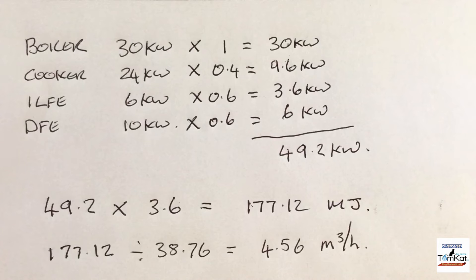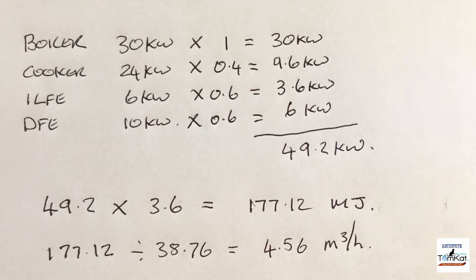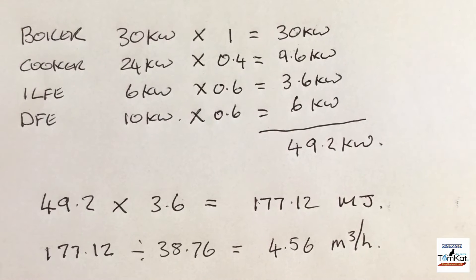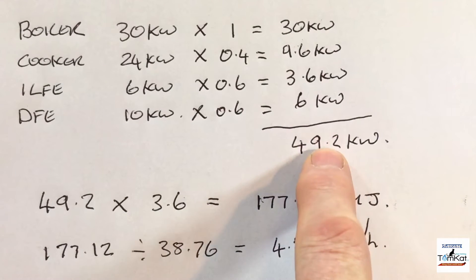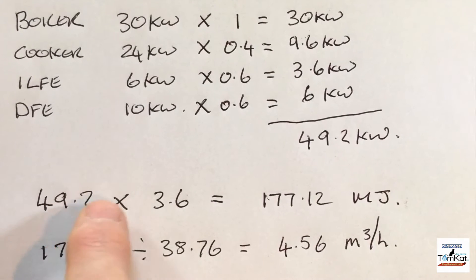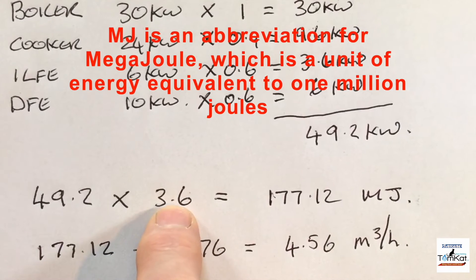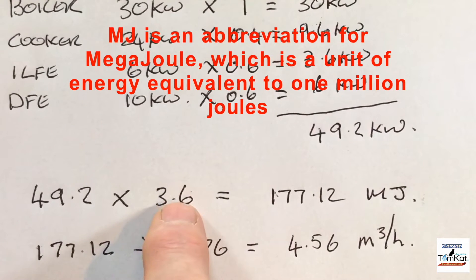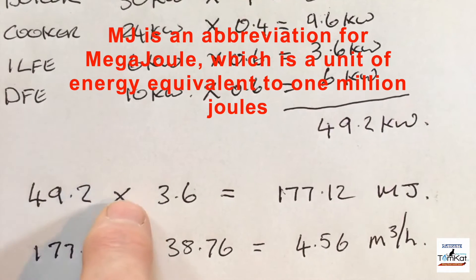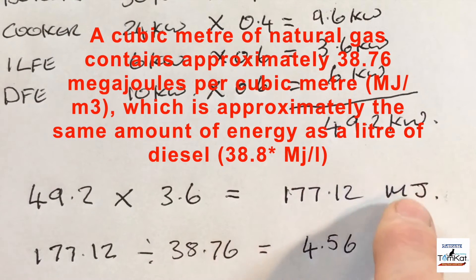Step two: add up the total gas load and convert the total kilowatt figure into megajoules. Our total load is 49.2 kW. We multiply by 3.6 because there are 3.6 megajoules in a kilowatt-hour. So 49.2 × 3.6 = 177.12 megajoules.